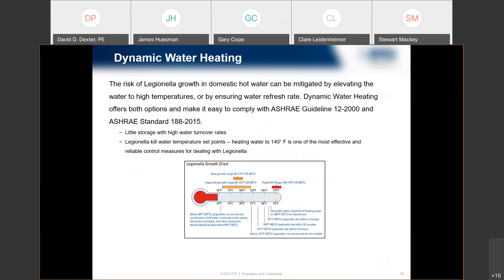If we're flowing water through a system creating 140-degree water, throwing it into the system, then blending it down to 120 for scald protection at the fixtures — at 120 degrees, legionella can survive. Unless you're killing it with contact time greater than 32 minutes, you're just passing legionella down the system and dropping the temperature back to where it can reproduce and survive. Contact time with chlorine and moving water are also factors, but the higher the temperature, the quicker the kill time.